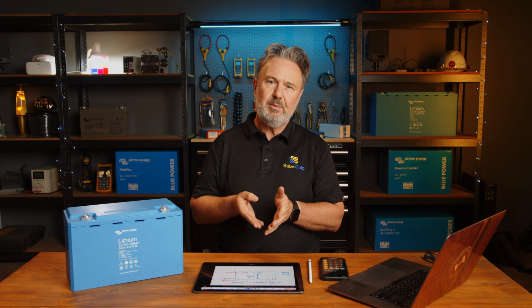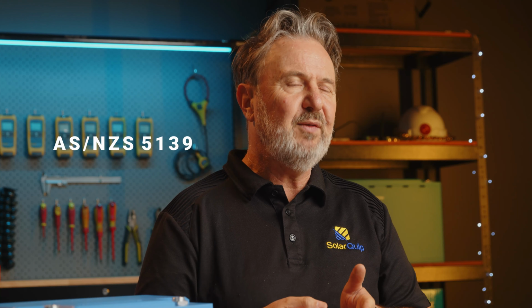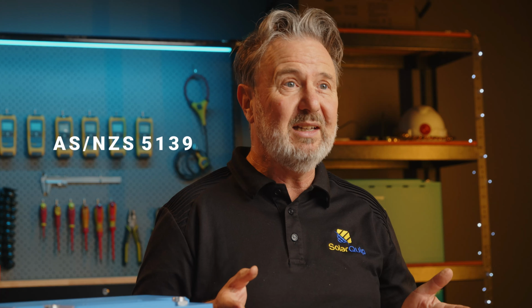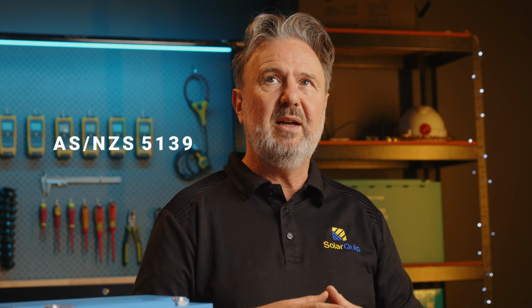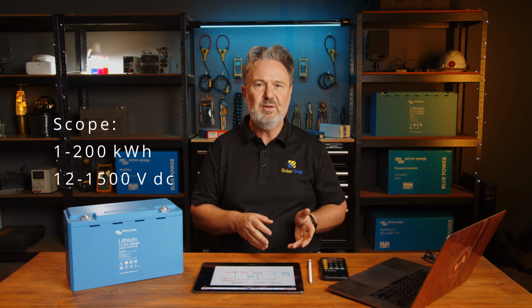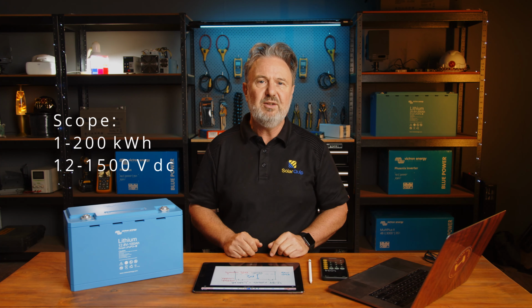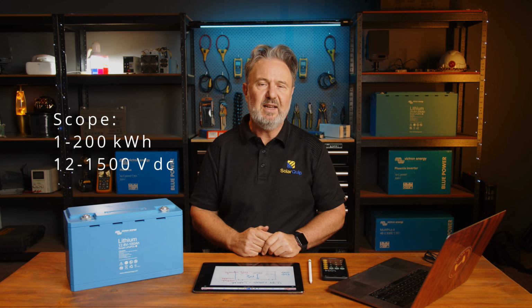What I want to cover lastly is a bit about our regulations in Australia and New Zealand around voltage levels and what you're allowed to work on. This is very specific to Australia and to some extent New Zealand. There's been a change in regulations for battery storage systems, with a new standard published over a year ago called AS/NZS 5139. It applies to battery systems installed anywhere connected to PCE, basically anything from 1 to 200 kilowatt hours of storage, from 12 volts to 1500 volts DC, a huge range. You need to comply with AS/NZS 5139. This may change with time, but at the moment it's not enforced in New Zealand, because New Zealand electricity regulations need to reference a standard, though it is enforced in all states and territories in Australia.